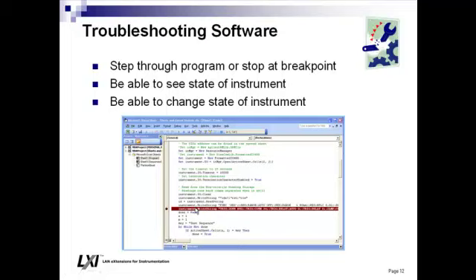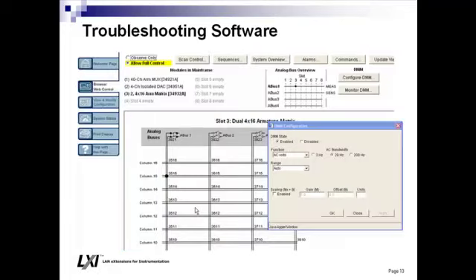You can change the state of that instrument, and with LXI you can bring up the instrument's web page to literally see what switches are closed or what the configuration of the DMM is. Automatically, you can see the state of the instrument because there's a built-in web server.